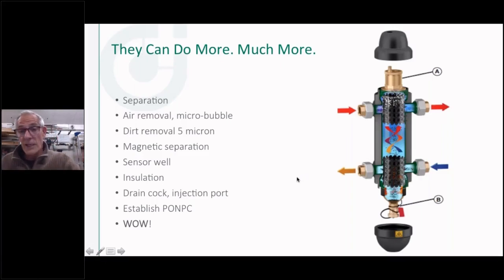So just moving along with this, as we progressed, we came up with even better ideas to make this even more user-friendly, give you more features, more functions in it. So we put a little bit better media in the top here so we can get better air removal. We can get those tiny little micro bubbles that you see when you churn up water, when you fill it for the first time, you've got that little cloudy water, which is entrained air and micro bubbles. So we put a little bit better air separation. And we did the same thing here at the bottom. We said, if we put a media in there, maybe we can get down to a 5-micron particle removal because they're going to collide. I call this a collision media. It's actually a coalescing media. Those little particles will collide as they come through there and drop out.